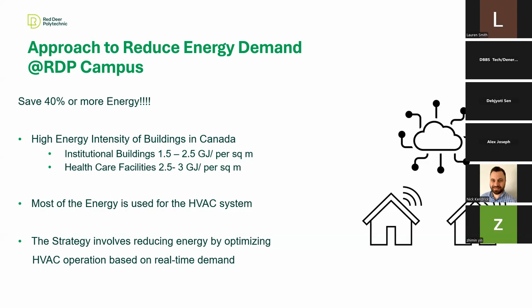So reducing the energy demand of the building by optimizing HVAC is a good way. Some people use a timer, since a building is occupied from 10 to 5 most of the time, so the HVAC runs at a certain capacity. But this does not work for buildings with seasonal occupancy, like institutional or healthcare facilities. There you need a monitoring system, similar to what Nick was talking about, that collects intelligent information about your building and tells the HVAC system through a control algorithm what to do.